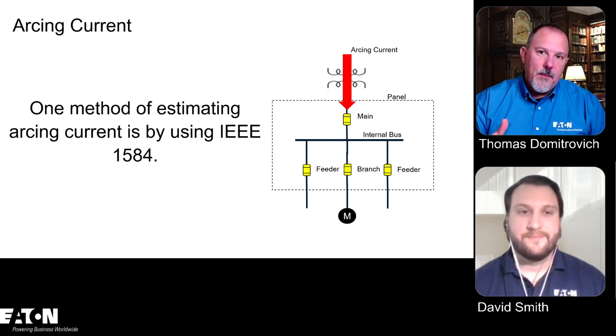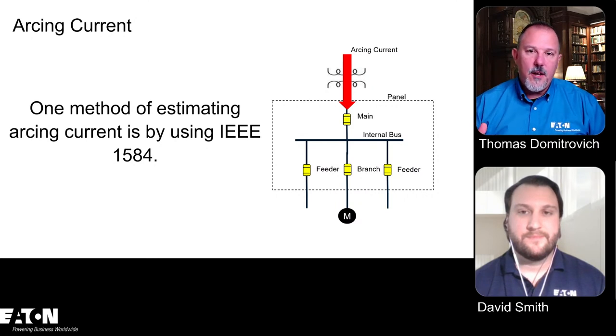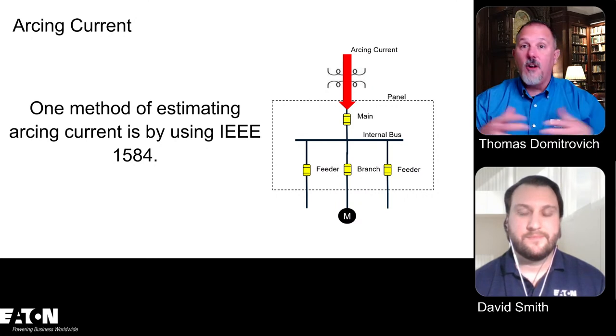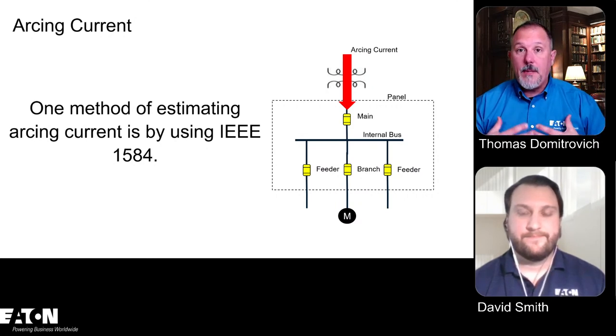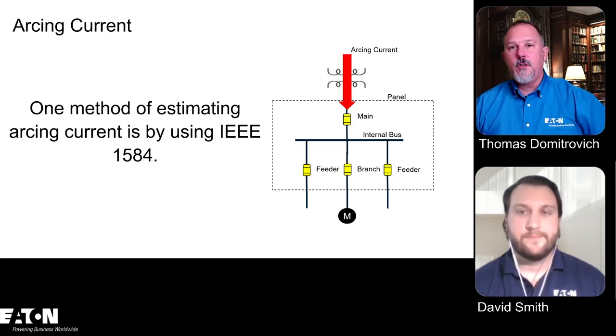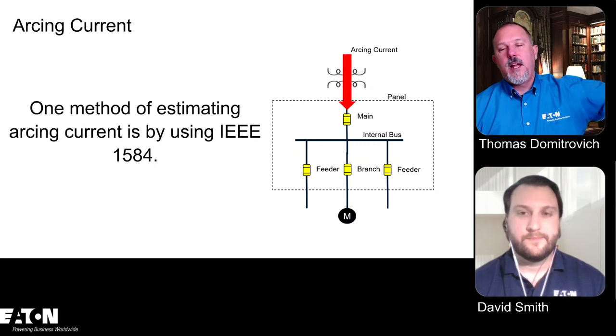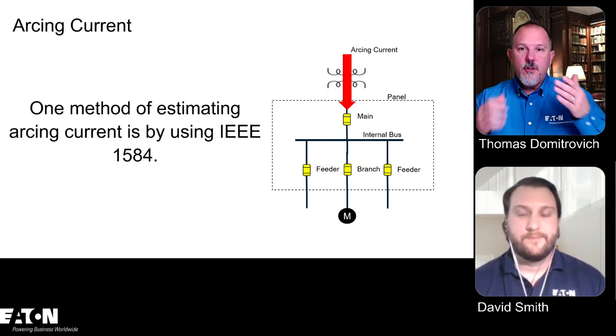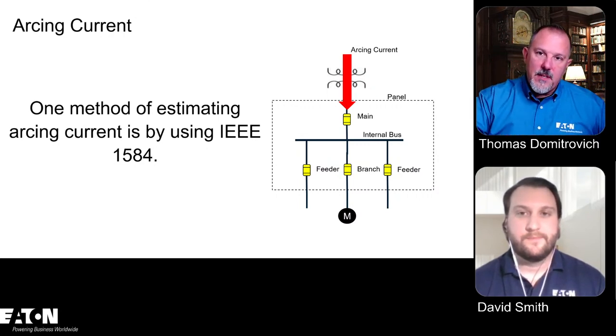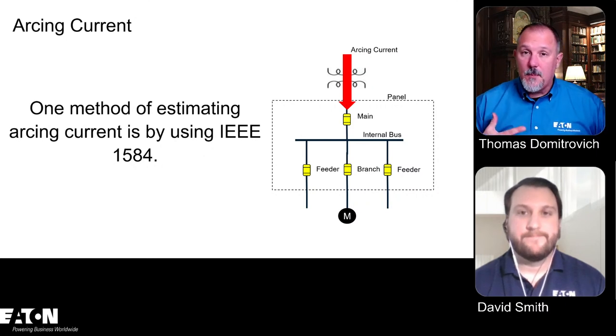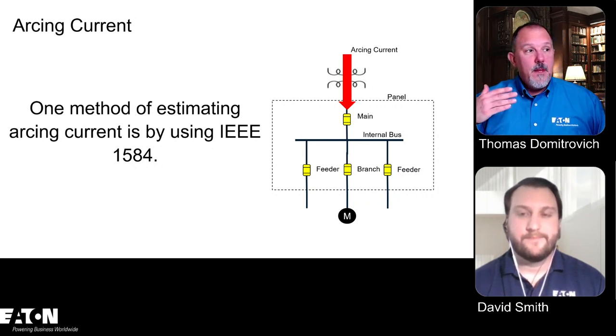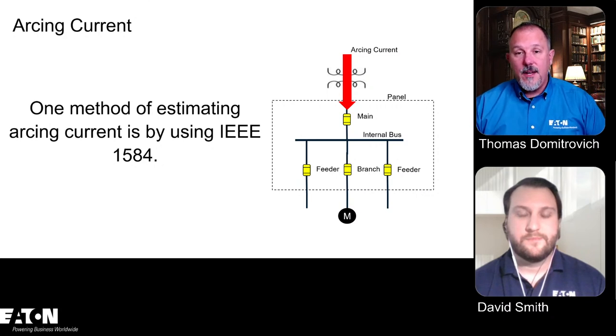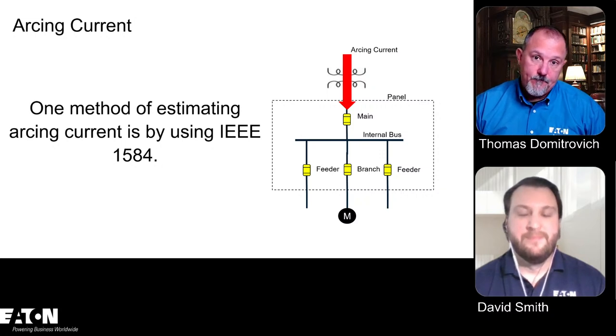But to Jim's point, if you're not in a labeled environment, our goal is to get people into PPE. It's estimating. You're going to estimate the available fault current. You're going to estimate the clearing time of an overcurrent protective device, and then you're going to make a decision based upon the table method in 70E to select your personal protective equipment. If you said on every one of those jobs you need to calculate it, that would make things much more difficult, and it probably wouldn't happen.